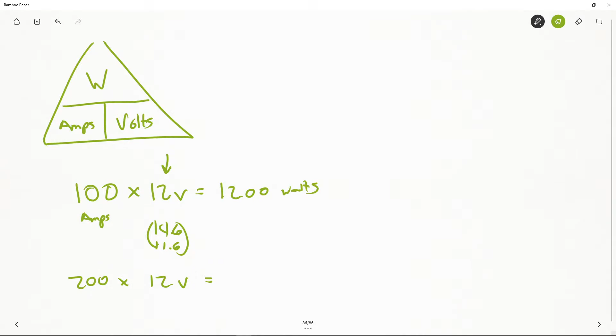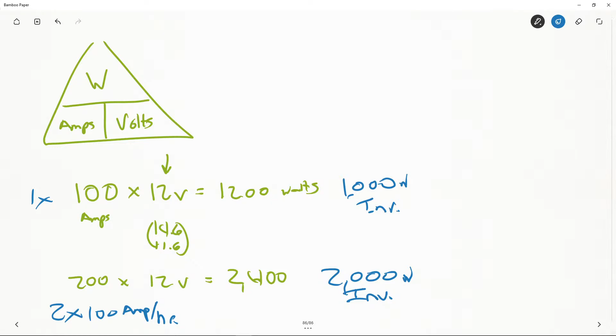So say you have 200 amps times 12, that gives you 2,400. This is why you need two 100 amp hour batteries, to run a 2,000 watt inverter. That's why they make that designation, and that's why you need at least one 100 amp hour battery to provide the 1,000 watts for a 1,000 watt inverter. Does that make sense?